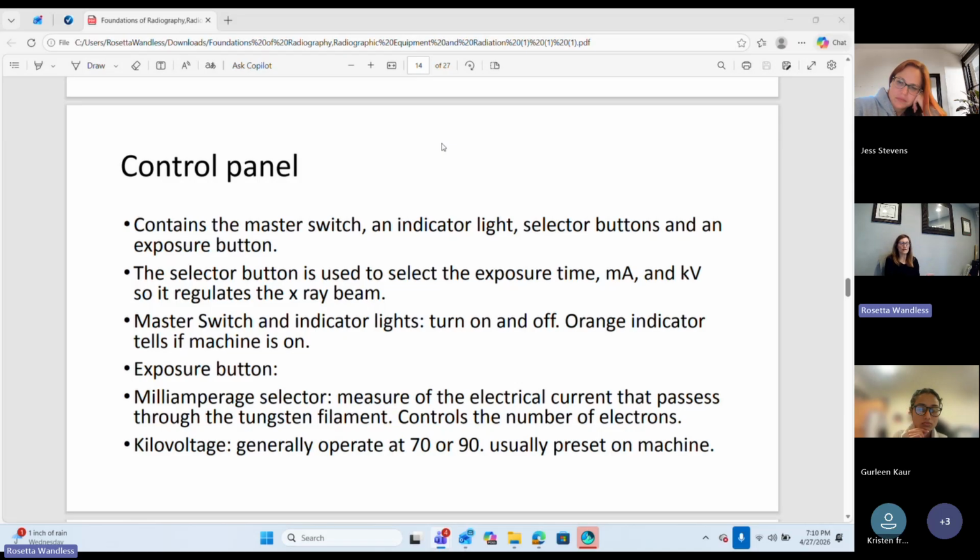So it is a range. We typically range the mA between 7 and 15. Okay, 7 is ideal, 15 is super high, but it can range on the control panel dependent on the frame of the human that we're taking an X-ray on, or the machine itself.